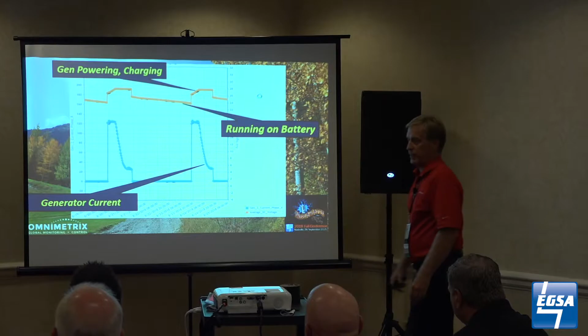Now, when you're charging lead acid, you commonly like to do that in a constant current sort of way. So what you see here is the genset current, and notice when it starts running, it has a reasonably flat top, substantiating that constant current charging technique. As the battery voltage rises toward being fully charged, when it gets there, the genset current starts to decline, indicating it's reaching full charge. When we get down here to the bottom, keep in mind we're not just charging, but we're also powering the site - that's why there's this baseline of genset current. It's not all just going into the battery.